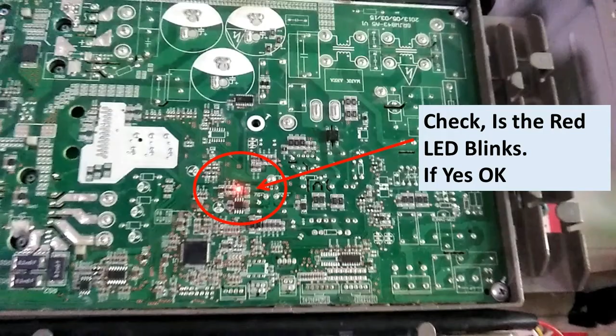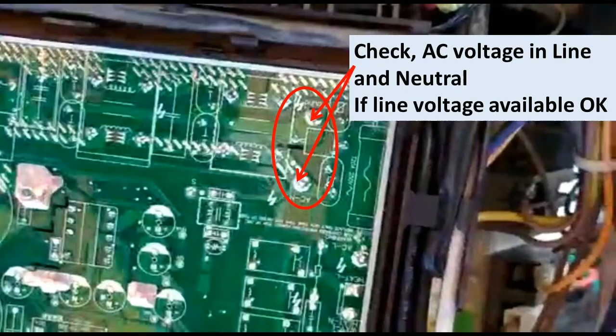So first of all, we have to check whether the LED in the ODU PCB is blinking or not. If the red LED is blinking, it means the PCB is okay and there is no fault in the PCB. But further, we have to check whether this green LED is blinking or not. In case of any defect, this green LED will start blinking, and we can refer to the chart given on the PCB cover or the error code chart.